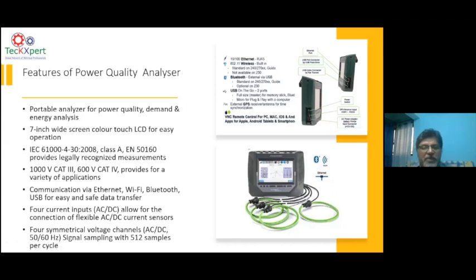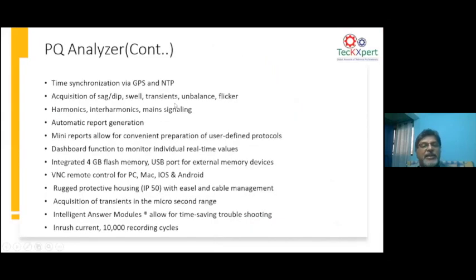So if you are doing a proper power quality study, as I explained before, you want to look at characterizing all types of power quality problems, starting from voltage transients, surges, overvoltage, undervoltage, notching, interharmonics. If you want to analyze all this, then you have to go for a Class A analyzer. This is a typical analyzer which will have a screen, with 4 voltage and current inputs. It can also communicate. That means you can have GPS synchronizing. You can have multiple analyzers at multiple points, synchronized with a GPS network, so that all the time stamping is done correctly.